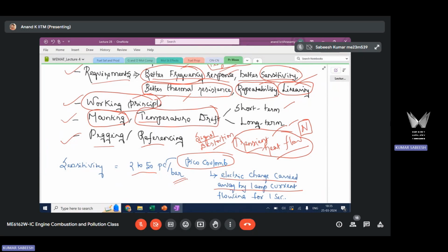And there are two types of drift. This is what is meant by drift. Drift is signal distortion due to temperature variation, right? The temperature variation is due to transient heat flow. The sensor elements are subjected to temperature variation due to transient heat flow, and this results in signal distortion. And this signal distortion is referred to as drift. There are two types of drift: one is short-term drift and the other one is long-term drift.